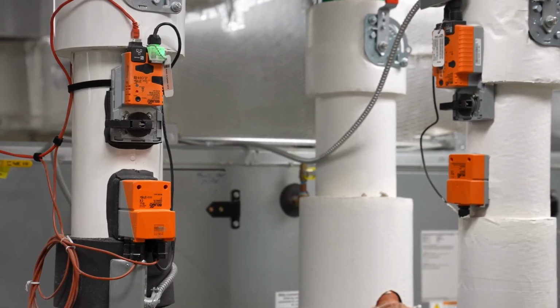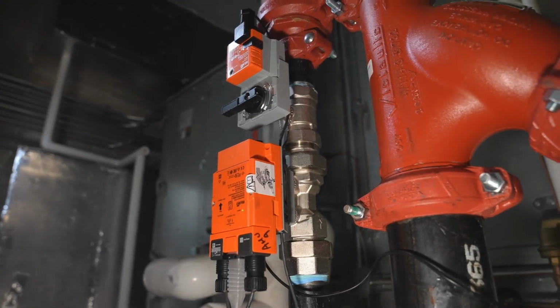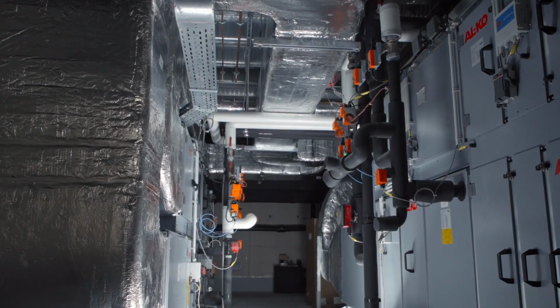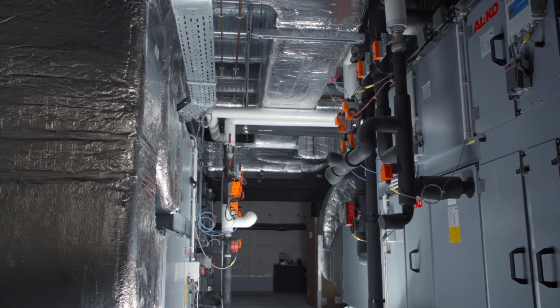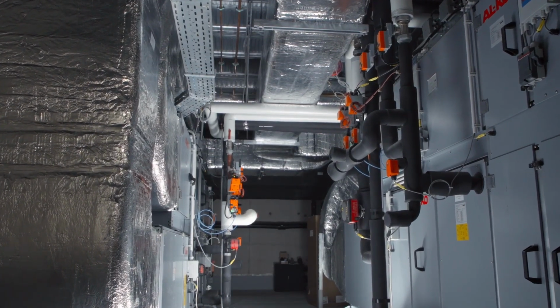The energy valve manages that delta T at the point of use, which maximizes dehumidification, increases the delta T at the piece of equipment, and then translates it back to the central plant, which optimizes chiller performance.